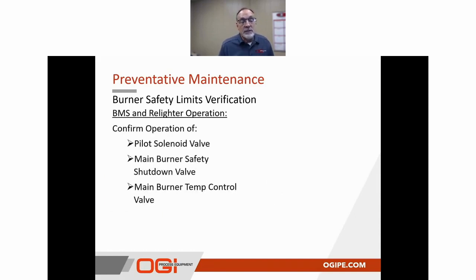The next thing we want to take a look at is, so we've gone through and reviewed the functionality of the safety systems that are a part of the burner. We've ensured that the controls and the instrumentation of the heater are in good shape, and we've gone through our visual inspections and our glycol inspections. So essentially, at this point, we're looking at the control that could be a part of the burner management system or a relighter system.